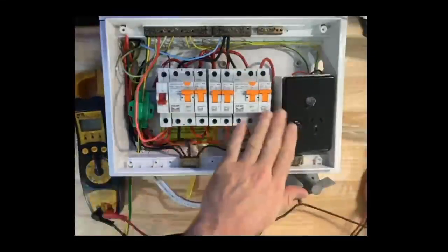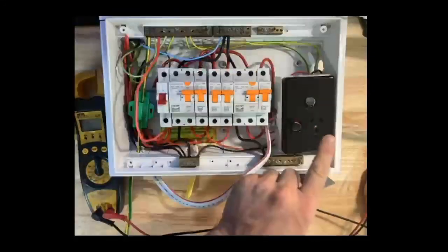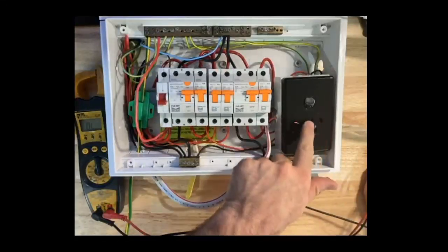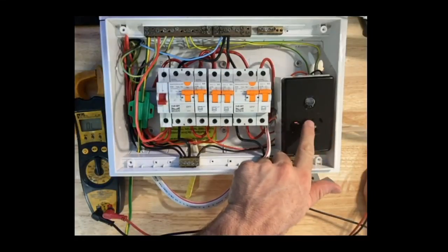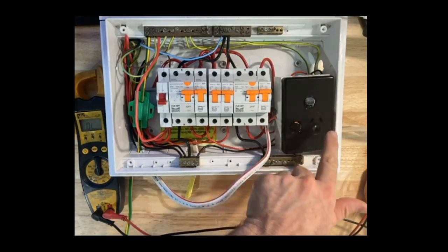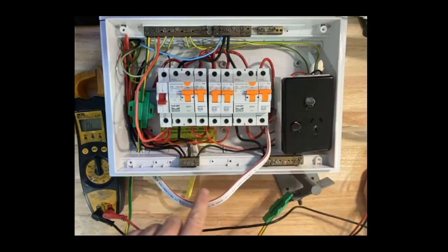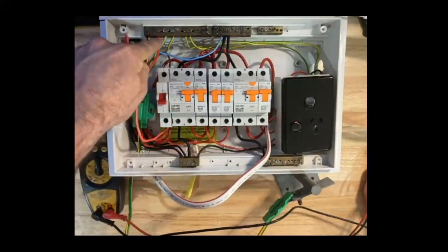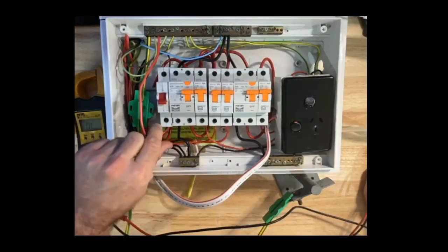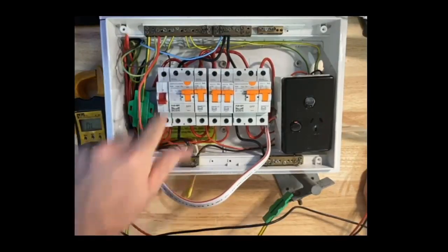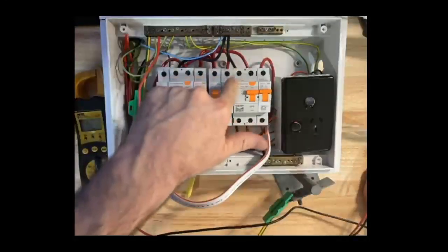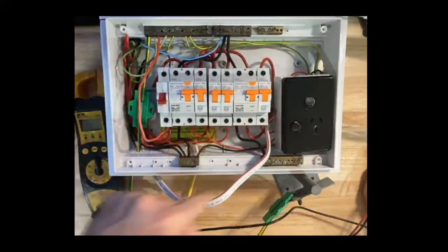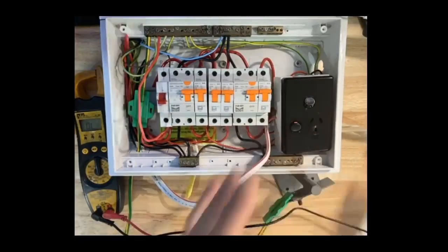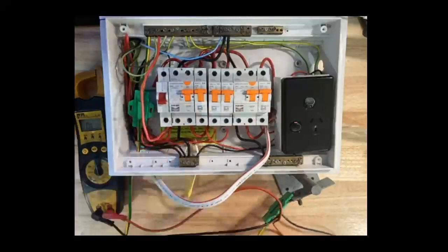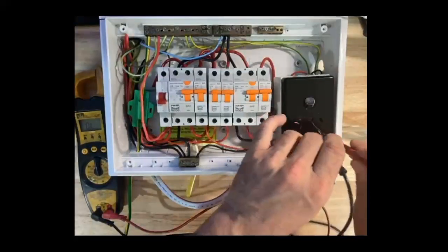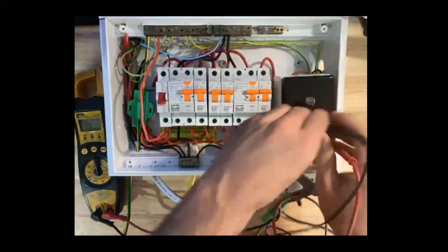If we imagine that I'm at this socket here, and this is in a different room to my switchboard, and I want to test that earth conductor, I can now go from the live conductor, test the live conductor to the earth conductor. So my test current will now go down the earth conductor to my earth busbar, through this wire that I have installed here, to my phase. All of my phases in the installation are connected off here, so it'll go back through my circuit breaker, onto that sub-circuit, and back to my live here. So now I should get a reading between my live conductor and my earth conductor right here at the socket.